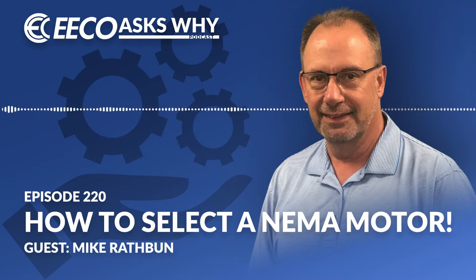There was one instance I'm thinking of, an aggregate, and this happened in the past, where typically most distributors or motor houses are stocking that design B motor. This was in a pinch and they had to get it going. They put it in, but it wouldn't start. I believe this was on a crusher or a very big conveyor, but it came down to it needed that higher torque on the front end. That was a learning moment for sure, but it goes to show you how important that NEMA design is. Very, very important factor there.